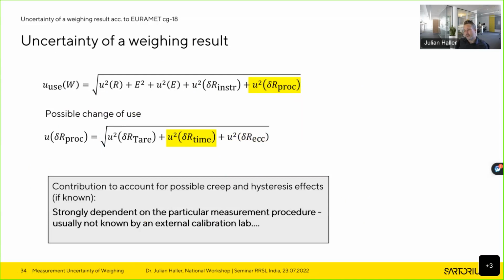Now, the detailed question: in dynamic weighing, does hysteresis play a significant role? What you do have is, sorry to say that, but the more quality the manufacturer has, the less hysteresis effect your weighing instruments will have. That's quite clear. But nevertheless, even for a high quality weighing instrument, if you weigh for a very long time, you do have an effect. In the weighing instrument you have mechanics, and this mechanics will have a hysteresis effect if you apply a load for longer.